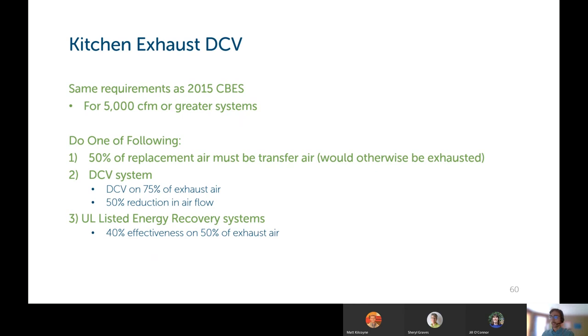Kitchen exhaust demand control ventilation. These are the same requirements that were in the 2015 energy code, where kitchen exhaust systems greater than 5,000 CFM must do one of the following to their exhaust air. Either 50% of the replacement air must be transfer air that otherwise would have been exhausted. You can do a demand control ventilation system. You need to do that on 75% of the exhaust air, and whatever you are doing the demand control ventilation on must have at least a 50% reduction in airflow.